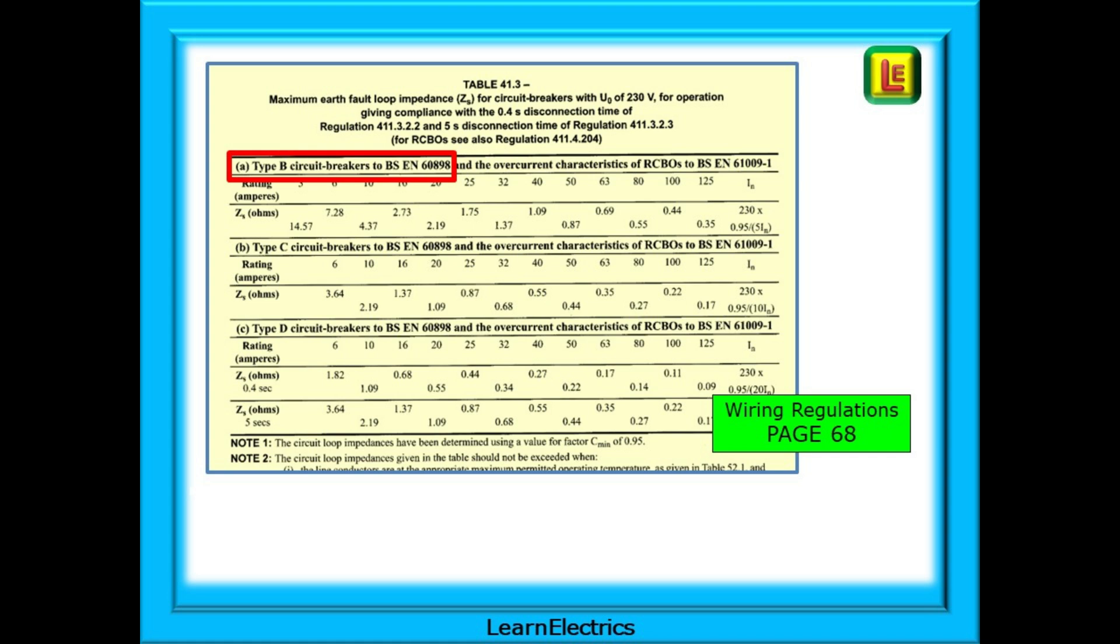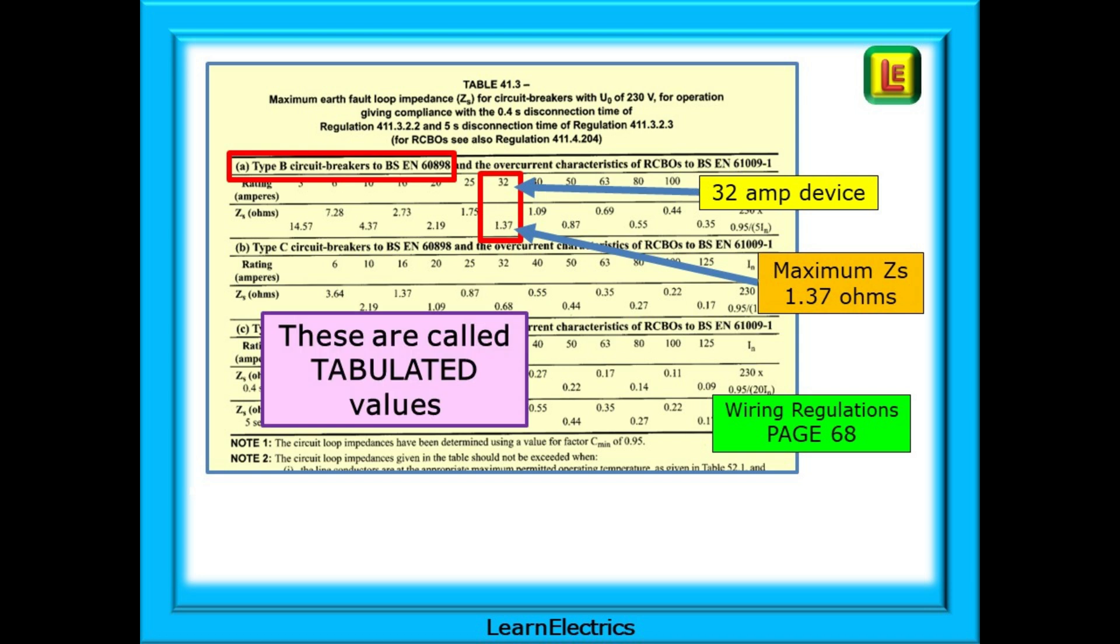Found the correct section for type B devices as highlighted in red here. Now find 32 amps and immediately below it is the maximum ZS value, which in our example is 1.37 ohms. These are called tabulated values. They've come from tables of ZS values in the regs book. Tabulated. It's important that you remember this.